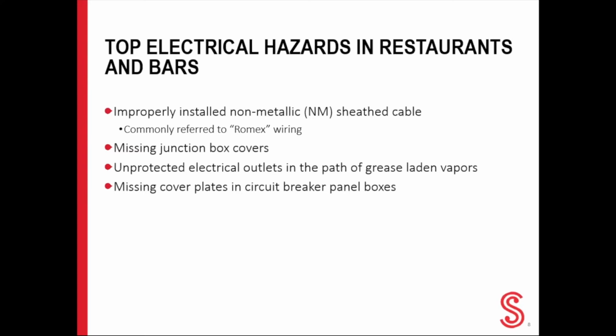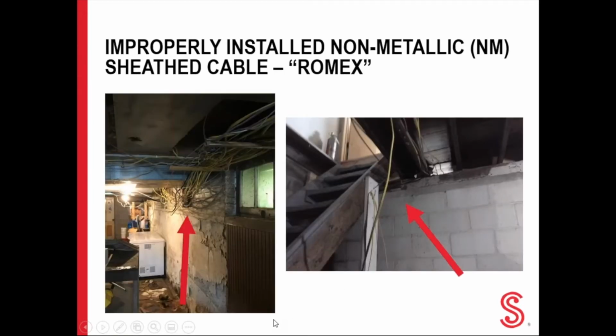So the topics that I'm going to be covering today are improperly installed non-metallic sheath cable, missing junction box covers, unprotected electrical outlets in the path of grease-laden vapors, and also missing cover plates in the circuit breaker panel boxes. So first up, we'll start with improperly installed non-metallic wiring. As you can see in these photos, these are examples of hanging wiring not being properly secured. All electrical wiring should be secured in accordance with the National Fire Protection Association 70 standards, or NFPA for short.